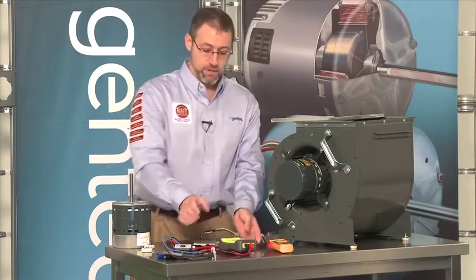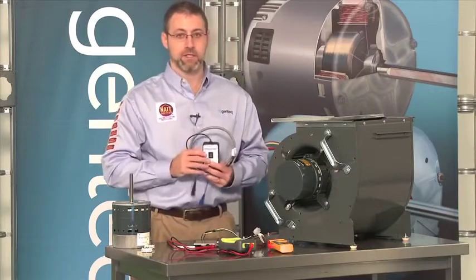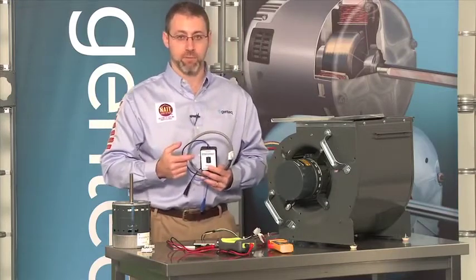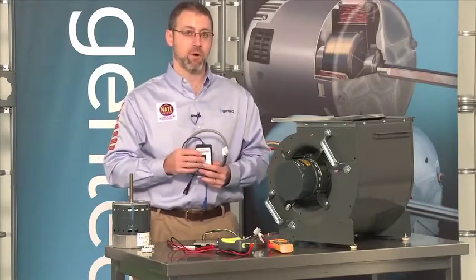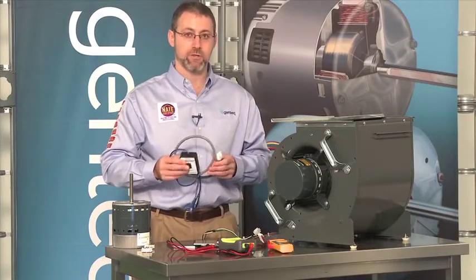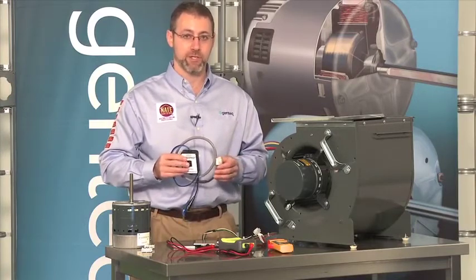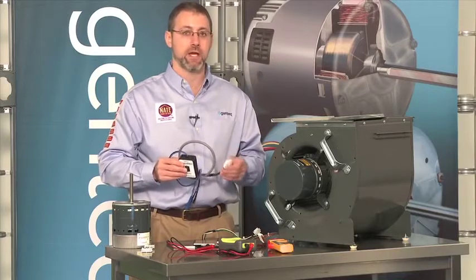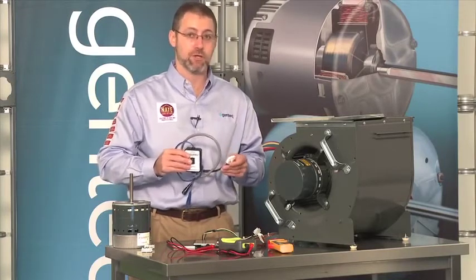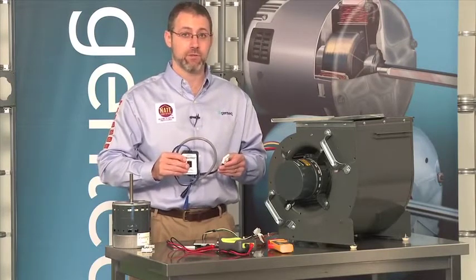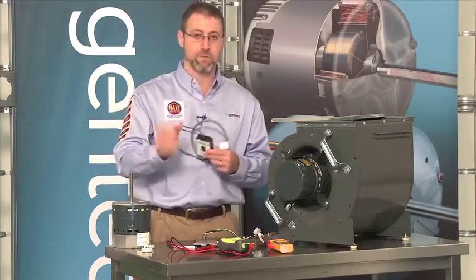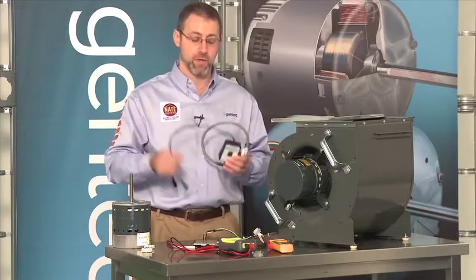For that reason, we've developed a tool called the TechMate, specifically the TechMate Pro. With the TechMate Pro, with the flip of one switch, you can get a go, no-go operation out of the motor. So we're not actually going to be checking the voltage or the communication coming to the motor. We're simply going to give the motor a good known communication and make sure that it works.